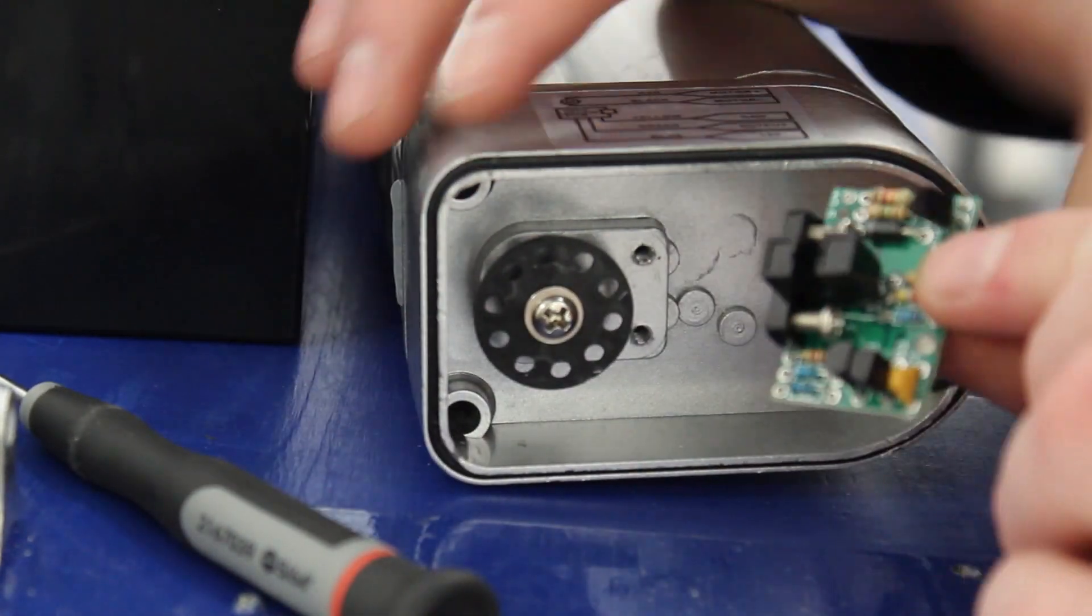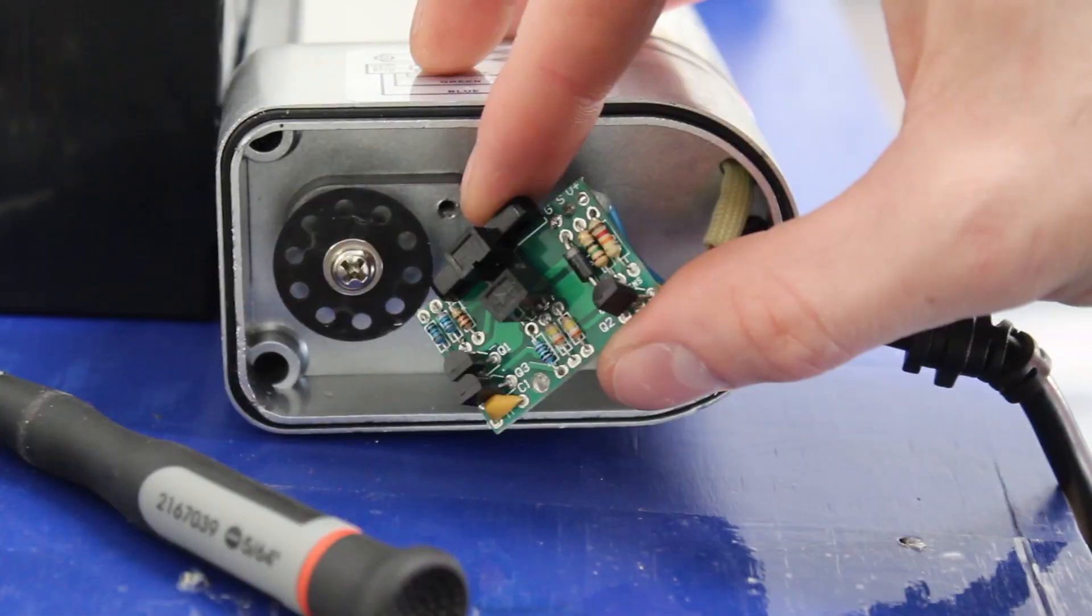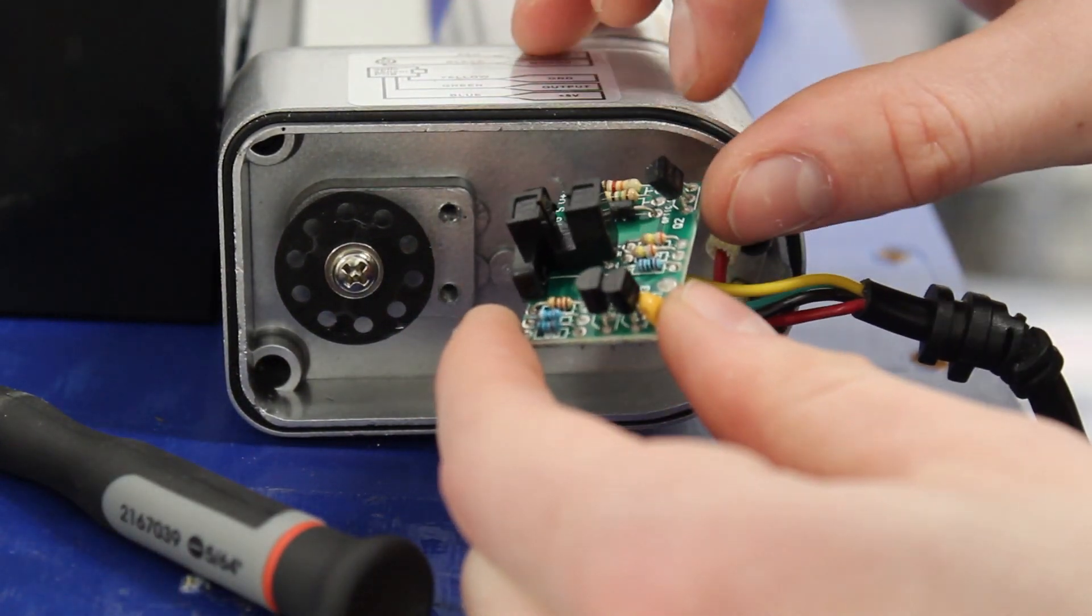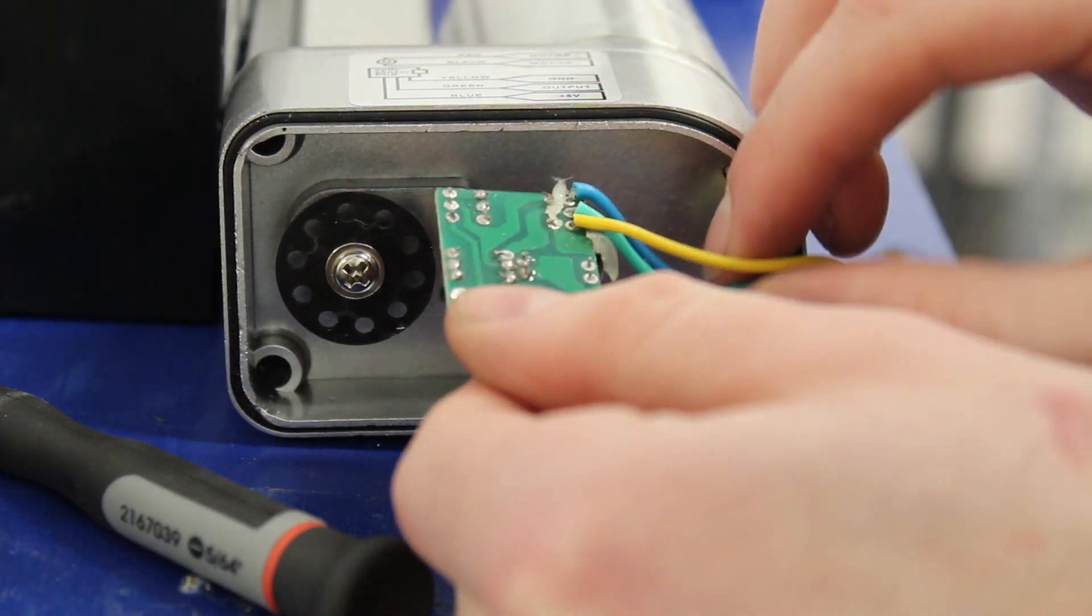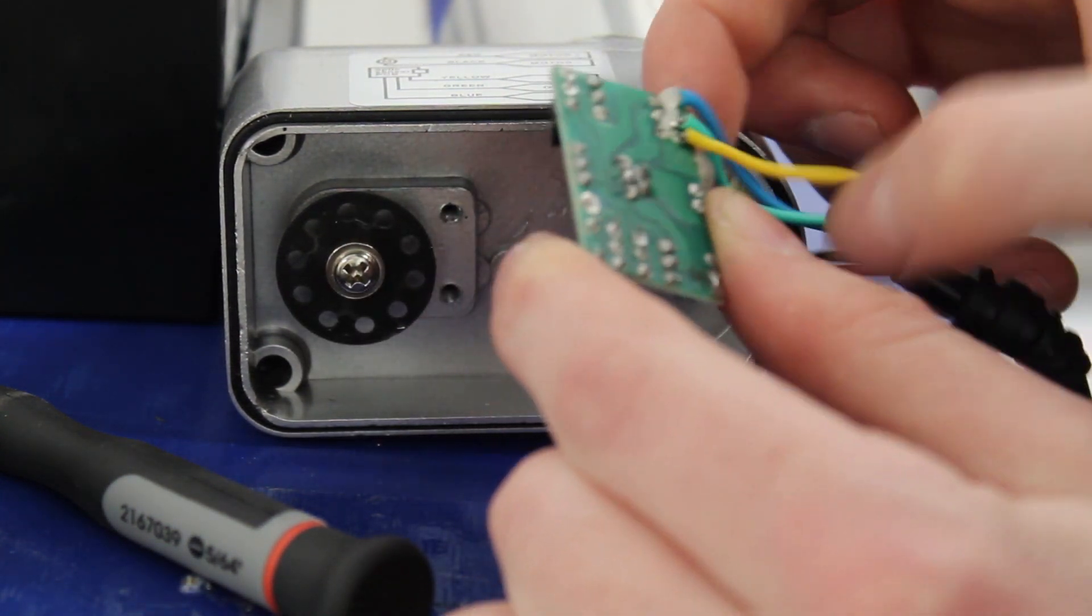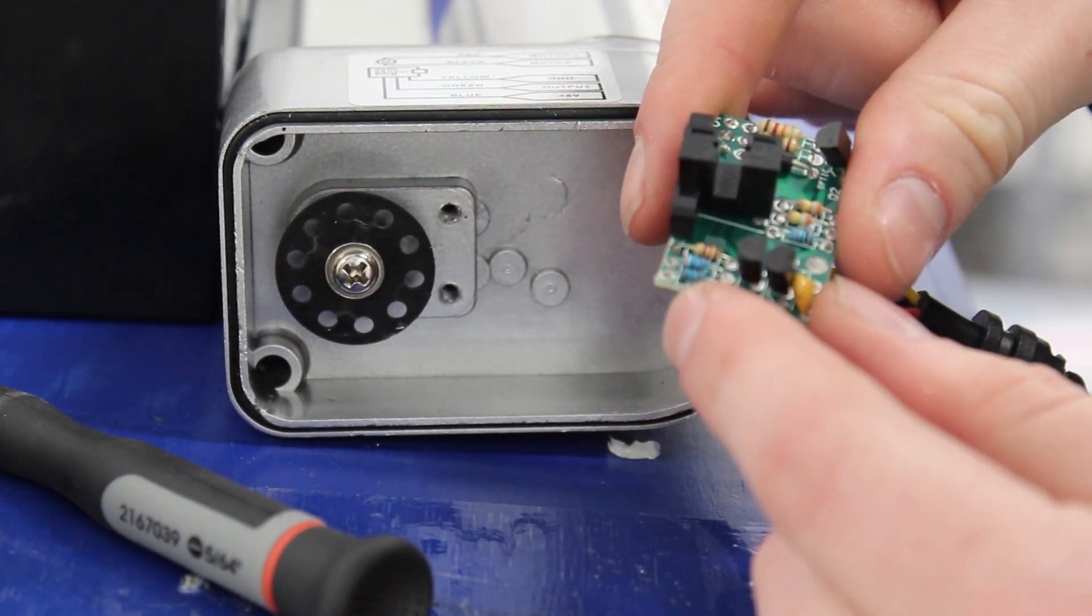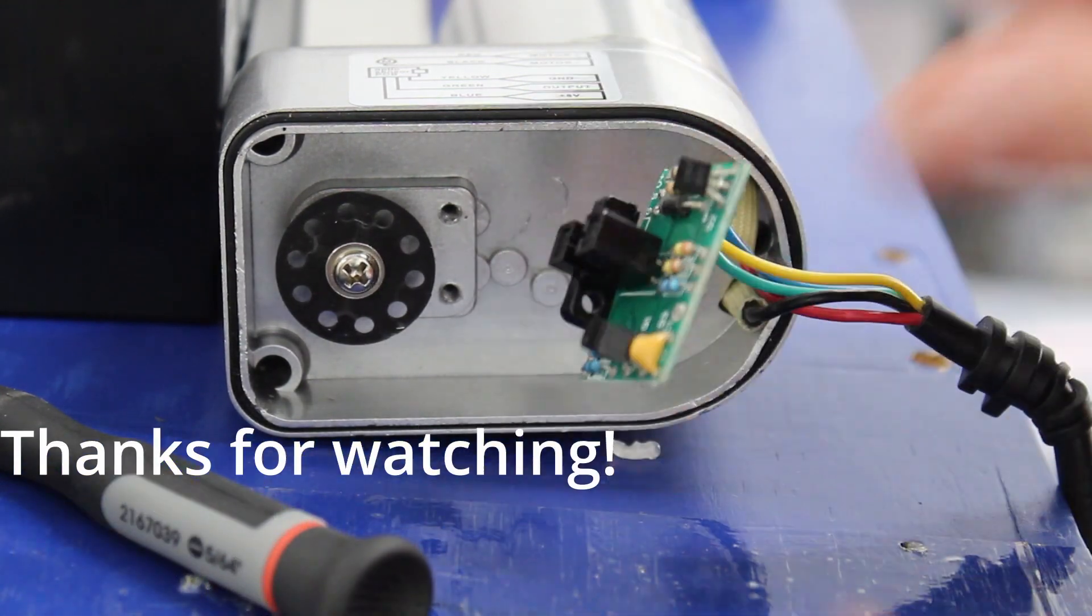The optical sensor is now out and I'm taking a look at the PCB board. I'm spotting it for any heat damage, any corrosion, or any worn connections or damaged solder. And if you look at the dead center of the board there, that looks like some damage. That is the sticky wicket. That is what is keeping the sensor from working.